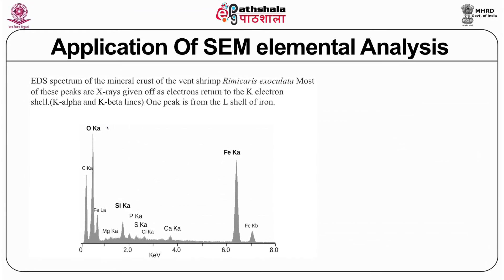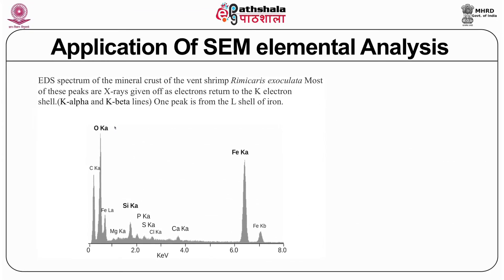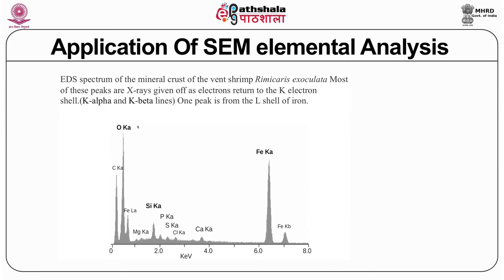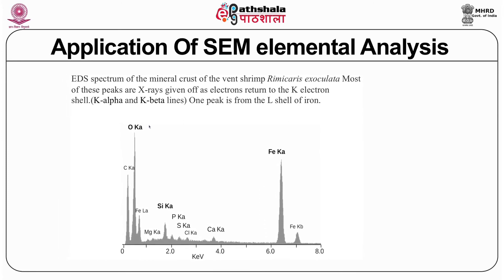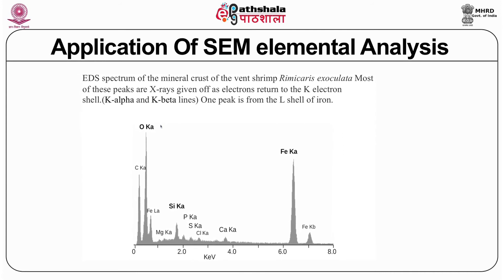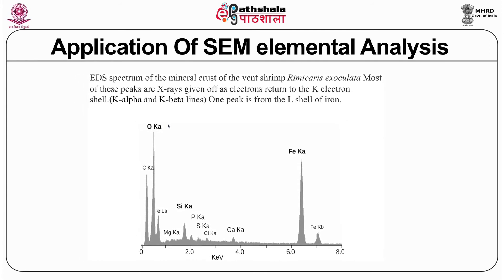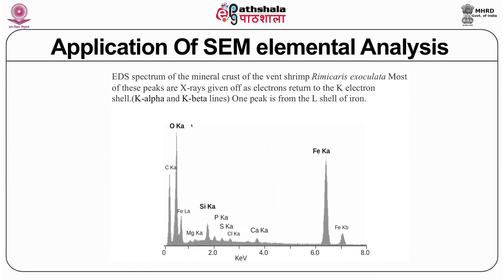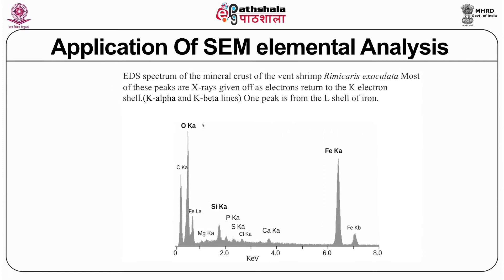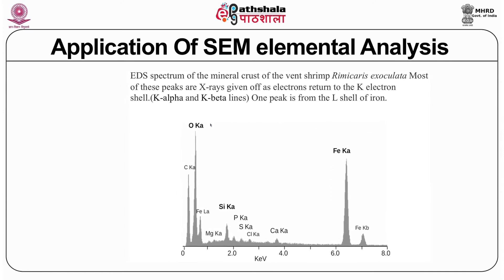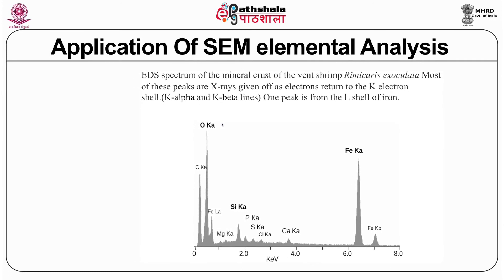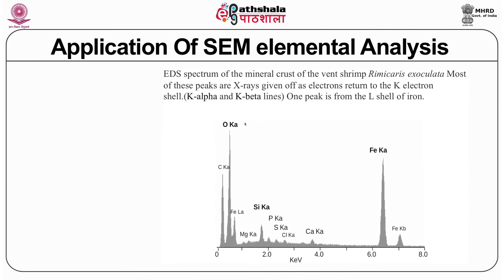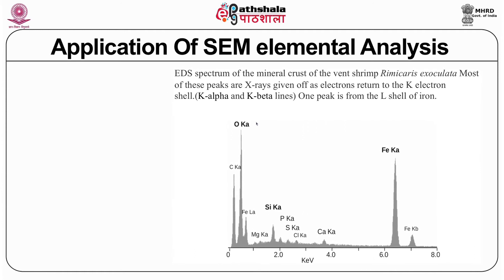This is an example of SEM elemental analysis: an X-ray spectrum showing elemental analysis. This spectrum shows a mineral taken from a reference, and most of the peaks from the X-rays are given off by electrons from different shells such as K electrons, K alpha, K beta, and so on. Each electron coming from a different shell gives a different energy level when it hits the sample and comes out, generating a spectrum that allows detailed sample analysis.